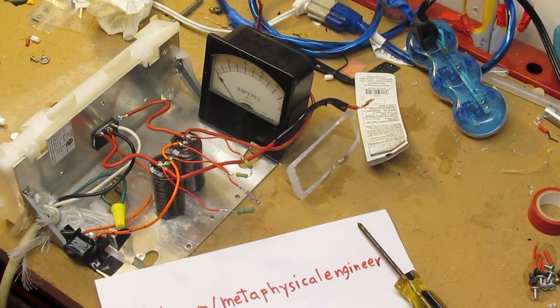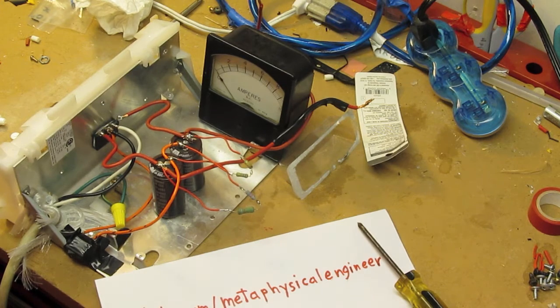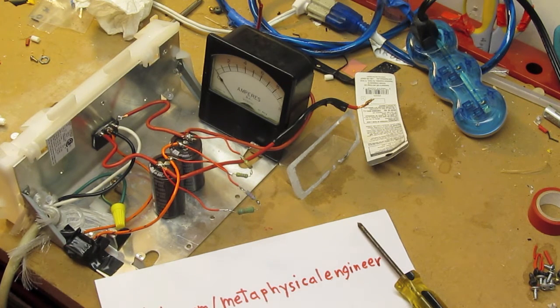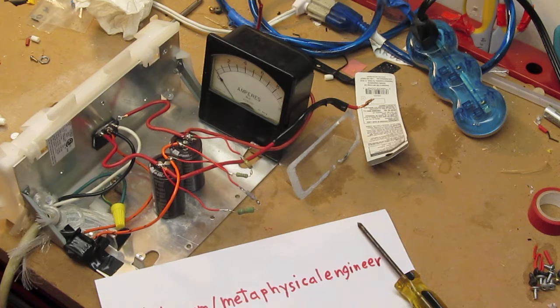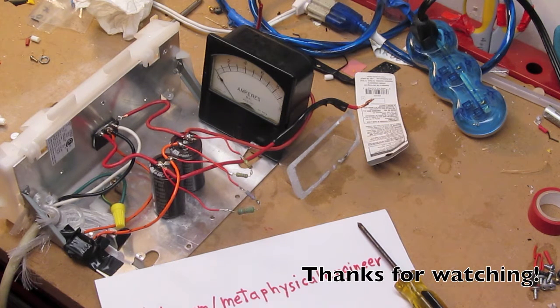Well apparently the camera batteries went dead and it shut off while I was tightening the bridge, but it's back on. I'll do some sort of load test at some point in the future. For now I'm gonna see how feasible it is to fire up a failed F15 T8 on an F40 T12 magnetic rapid start ballast.